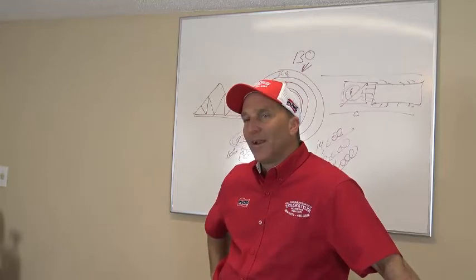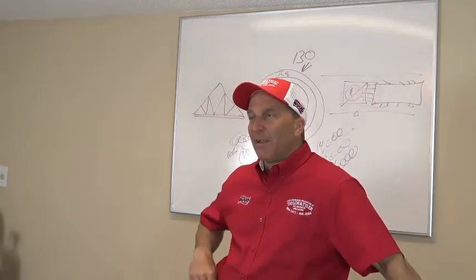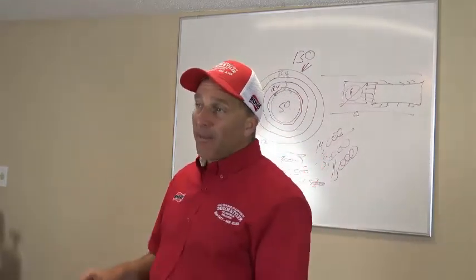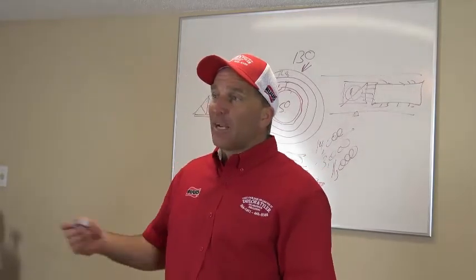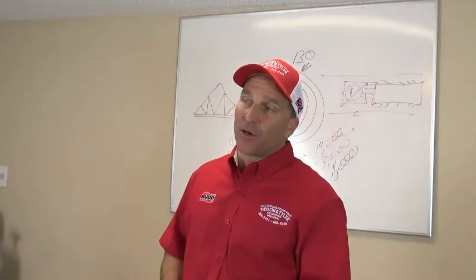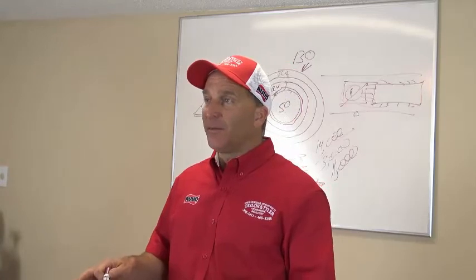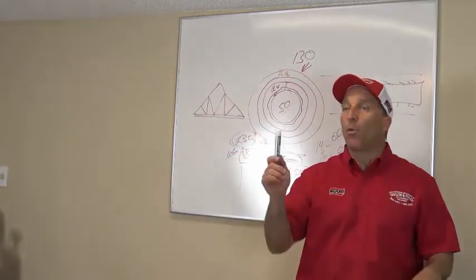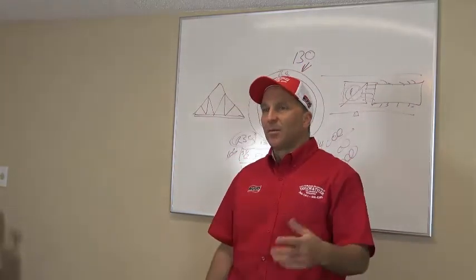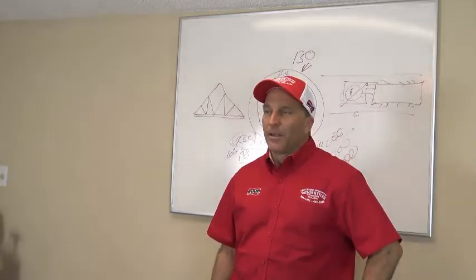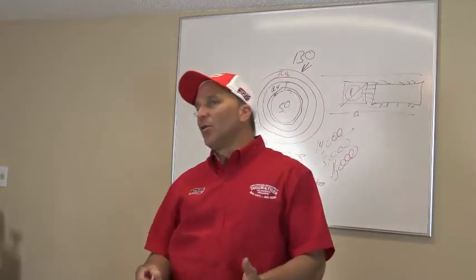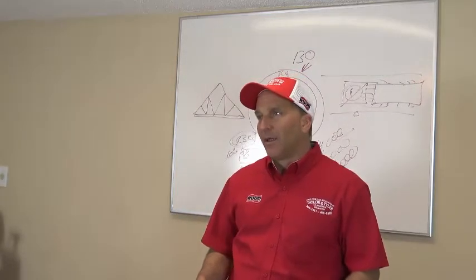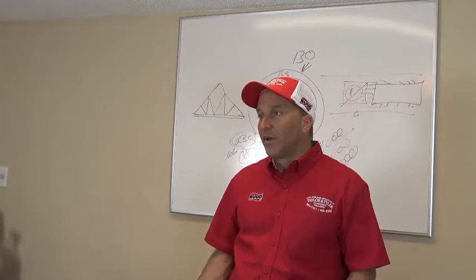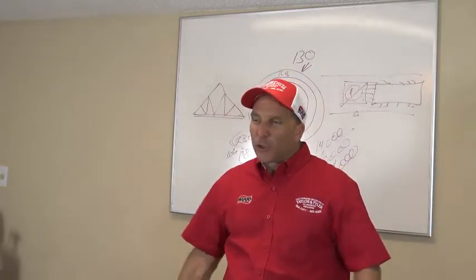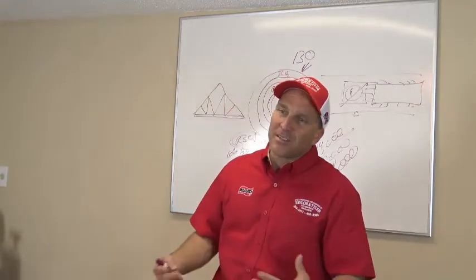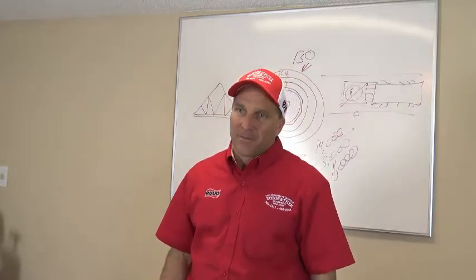It's just stupid. You know, I mean, so you've got to be able to explain it. And if whoever put the fan motor on would have said that beforehand, or while he was at that job, then he would have called back and just said, "Okay, you told me the fan motor was probably going to go bad. Come on and put a new fan motor in." But since nobody said anything, oh, you caused it. Right. Okay? "You caused it because you put water on my condenser." Sir, it rains all the time in your system. "Yeah, but you shot water up in it." Sir, it's been raining on your condenser for the last 12 years. If water was going to get in it, it would have got in over 12 years. It's a sealed motor. "So no, but he was shooting it in horizontal." It don't rain horizontal. Sir, it pours down raining on your system for 12 years. That thing was back there for Katrina.